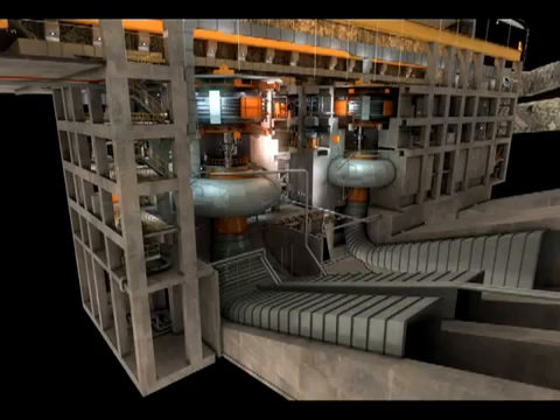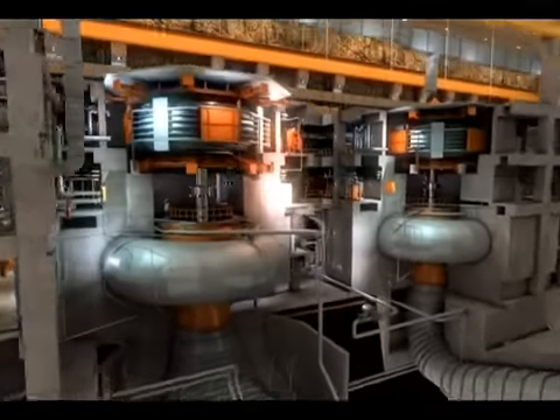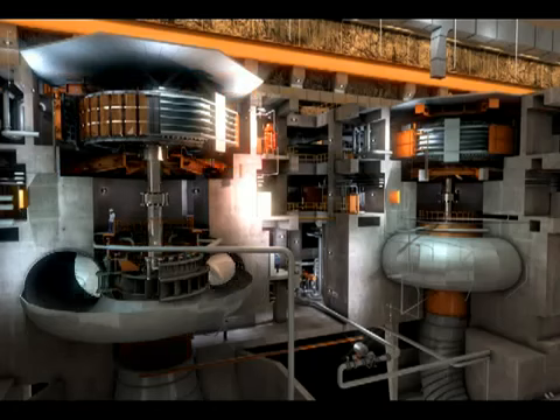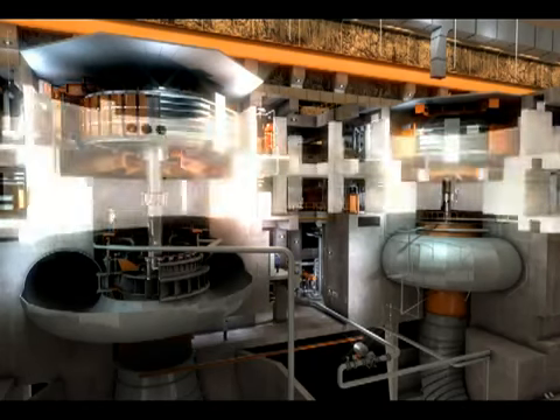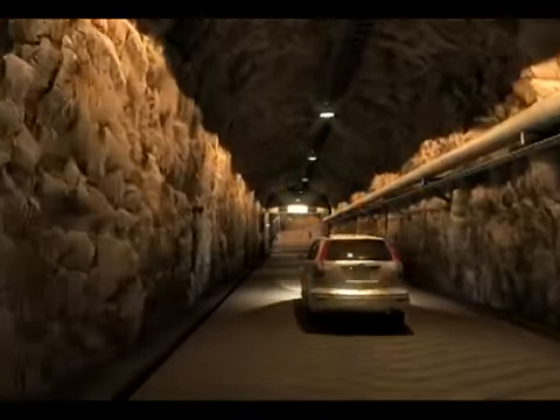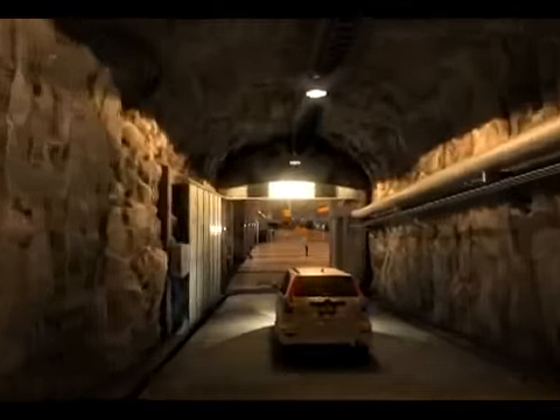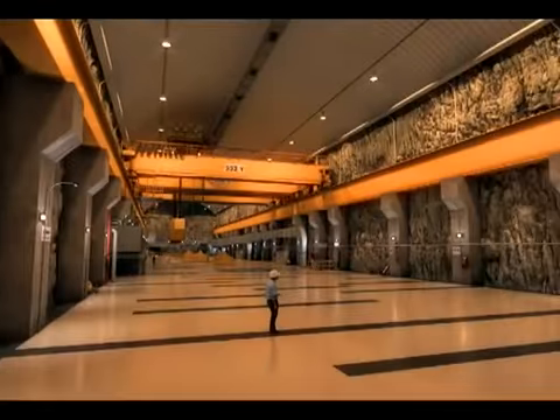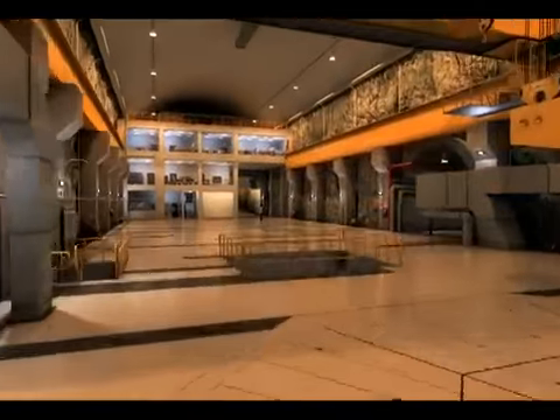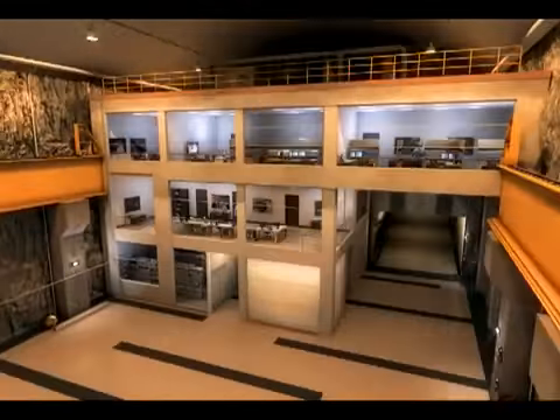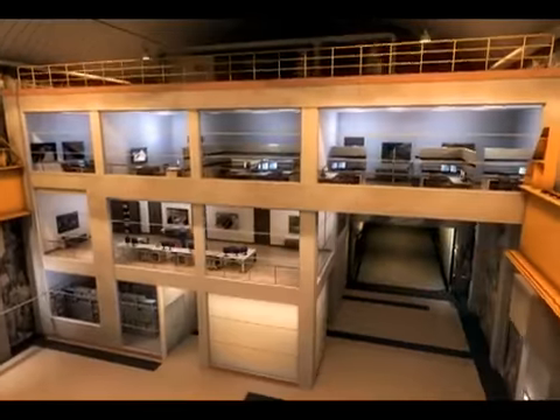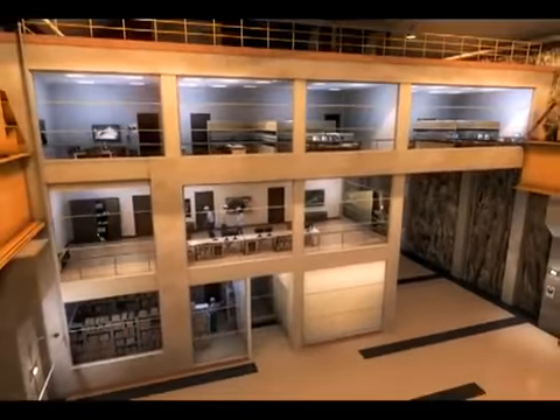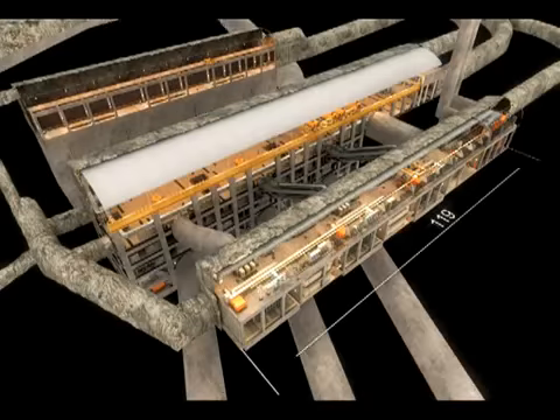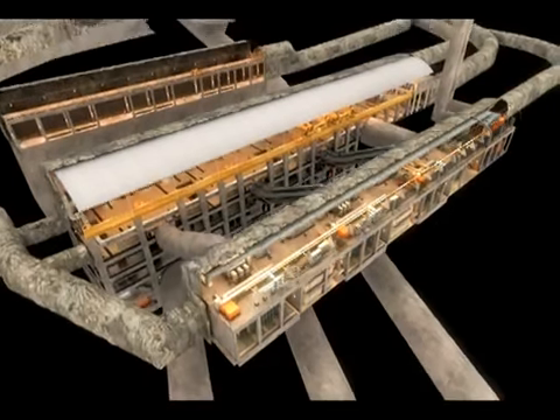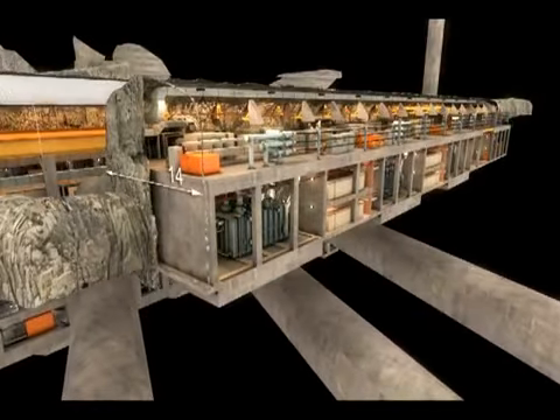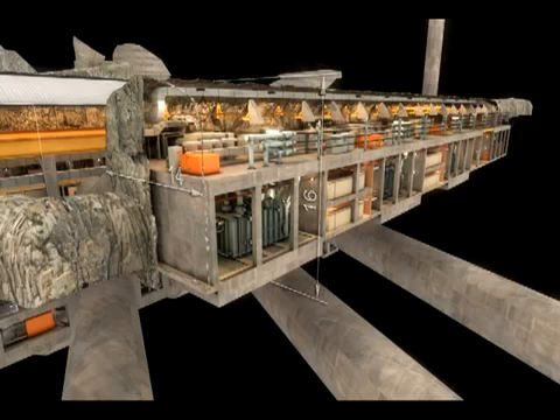The bottom level is known as the pump floor. The generator equipment is on the turbine and electromechanical equipment floors. The main floor is where the personnel arrive when they enter the underground station. The erection area and the control building are also located on this floor. The transformer cavern is 119 meters long, 14 meters wide and 16 meters high.